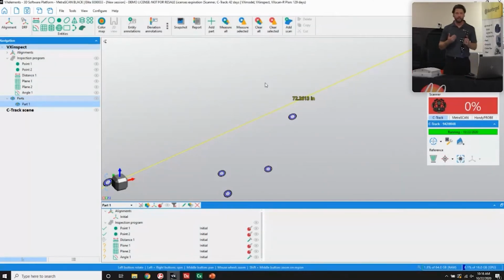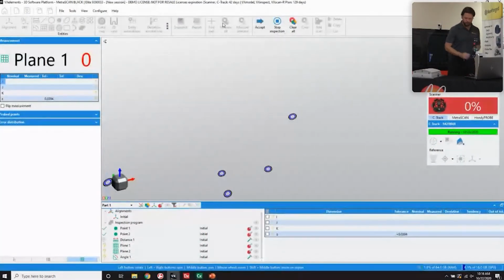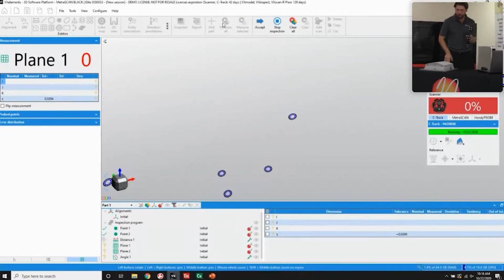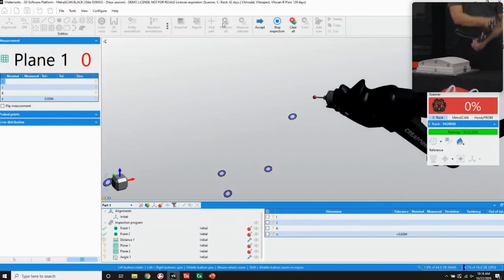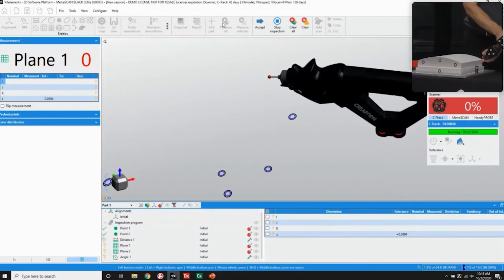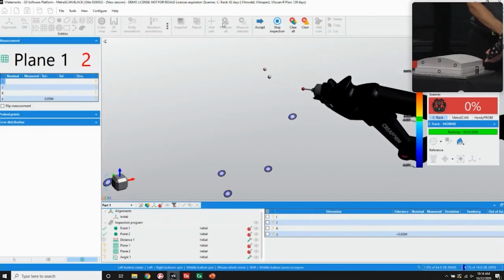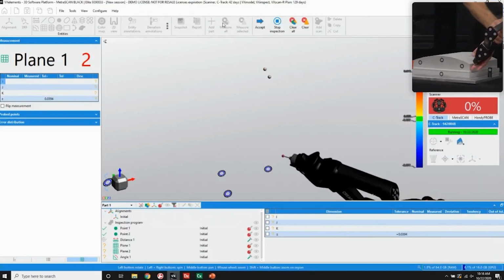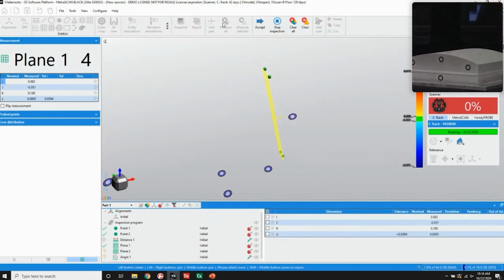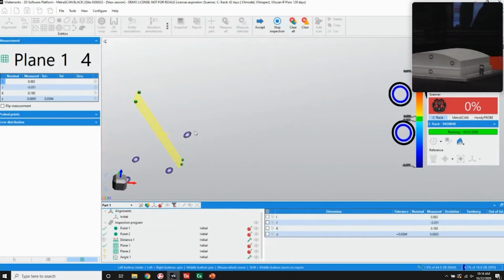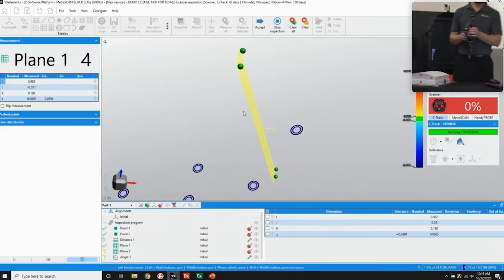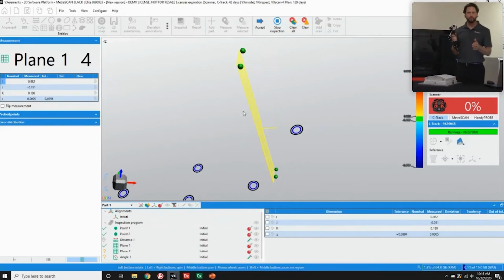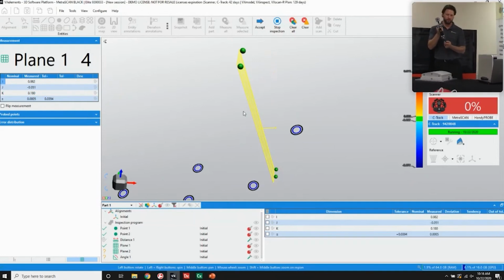If I want to do something like take an angle, I'm going to make an angle between this plane and this plane here. So we'll take the probe and touch it to the part. Click 1, 2, and you see the plane building here in my field of view. 3 and 4. There we go. So there's a plane. Now I'm using a 6mm ruby, so it's taking the points and compensating 3 millimeters in the direction of the edge of that ruby. So extremely accurate. You're supposed to touch the ruby up to it. If you're familiar with 3D scanning, where you're taking a whole bunch of scan data, a whole bunch of triangles, and you have vertices between those triangles.